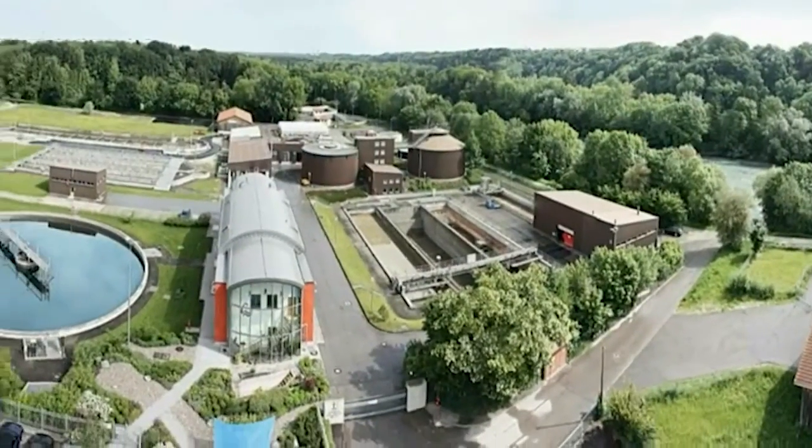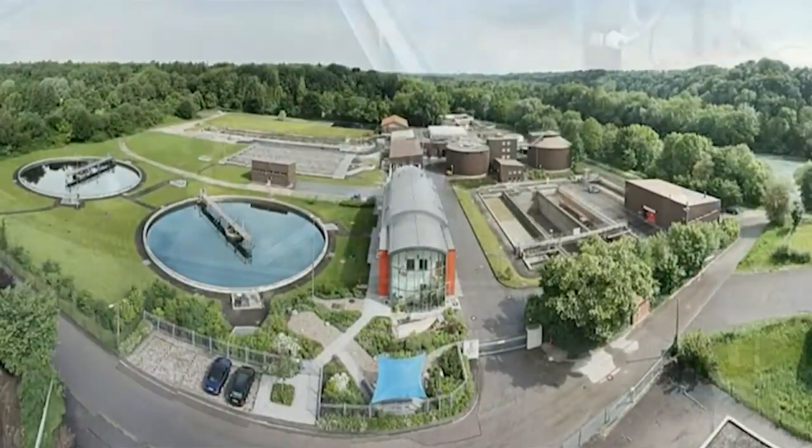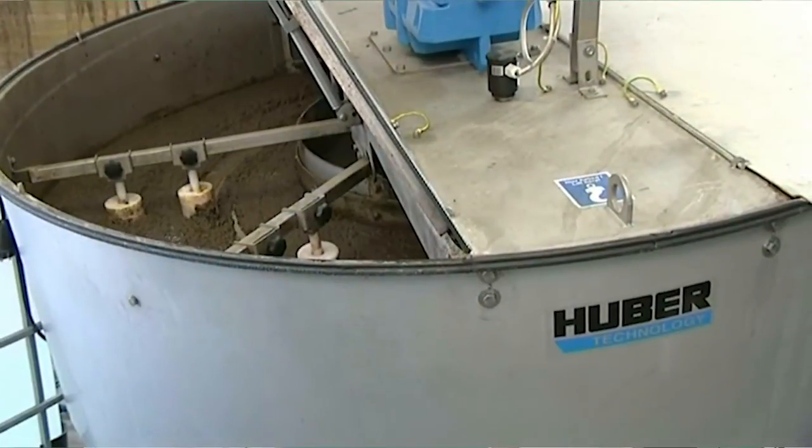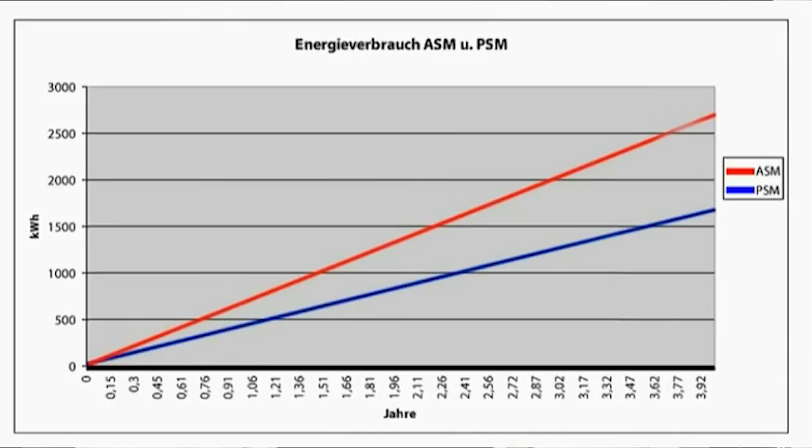In some applications we get a break even point after one year. We did a real test in a waste and water treatment plant near Munich and we put the PMSM motor on the same gearbox. It was a disc thickener application and compared the asynchronous motor in IE2 to the PMSM motor in IE4. And the result was very positive. We get an energy efficiency of about 40%.